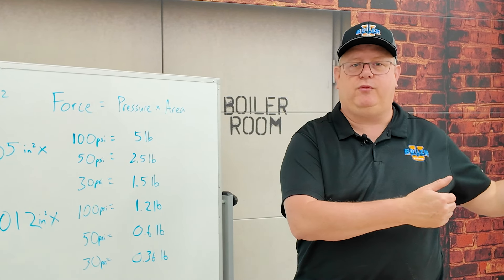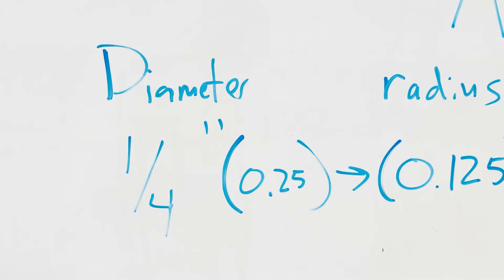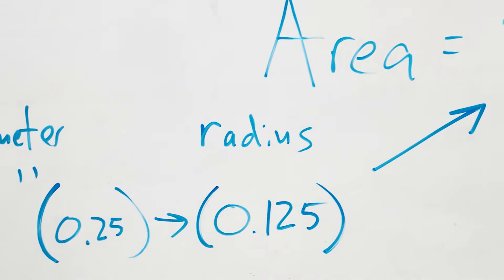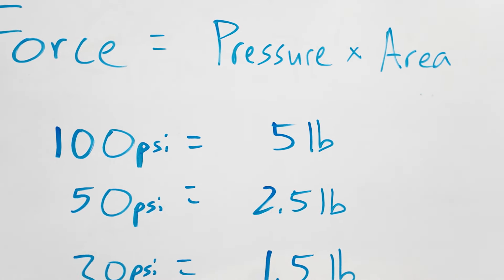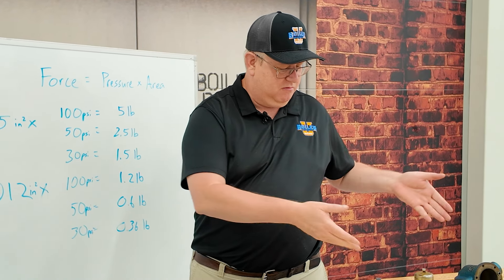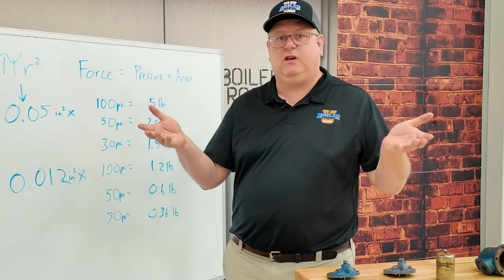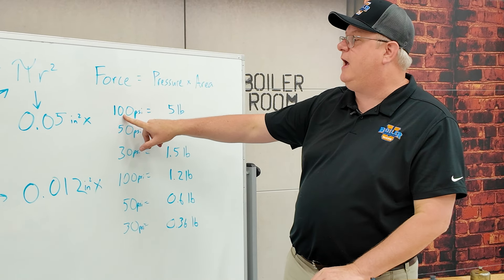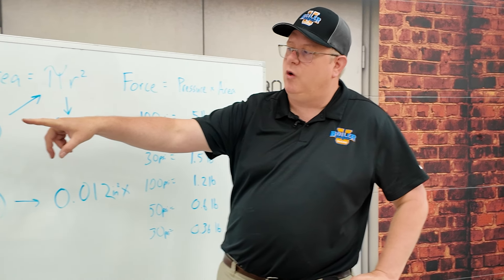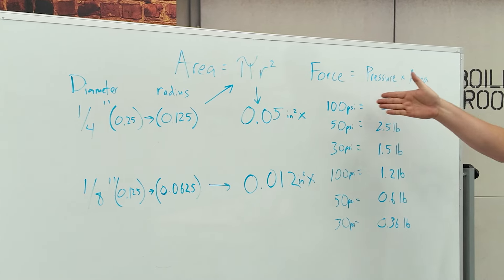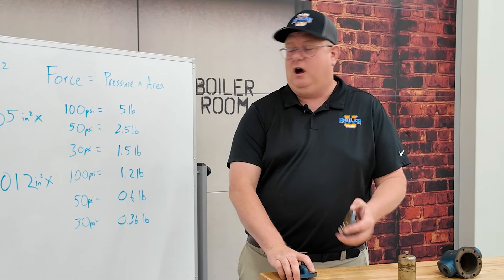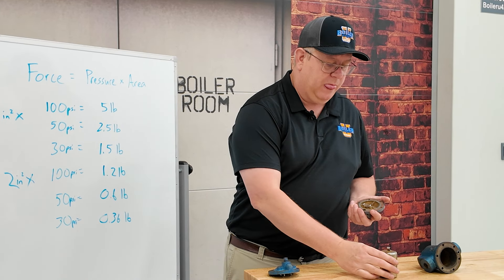For our purposes, we're going to assume the downstream pressure is zero. If we look at our trap with a quarter inch orifice, we take that diameter, cut it in half to get the radius, run it through our pi times radius squared equation — that gives us the surface area of that opening. In an application with a proof pressure of 250 PSI and I put it on a 100 PSI application, that quarter inch orifice area times 100 PSI gives us a total force holding this trap shut of five pounds.